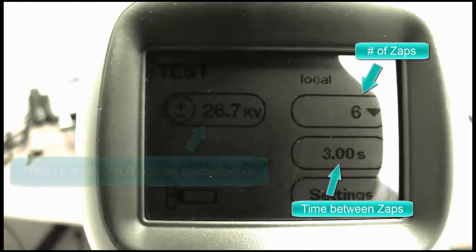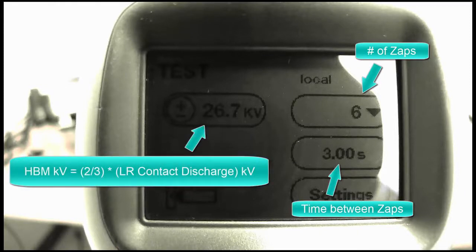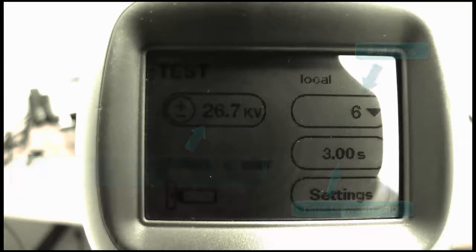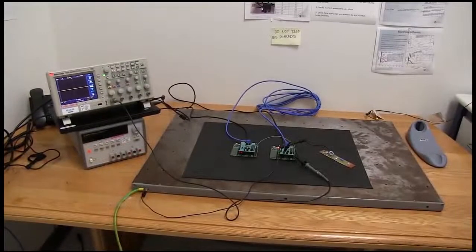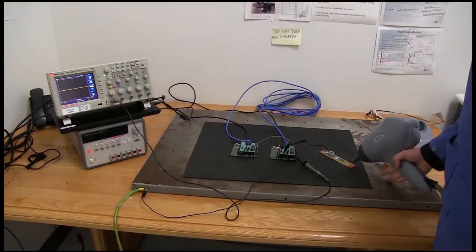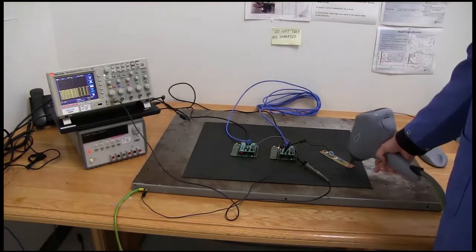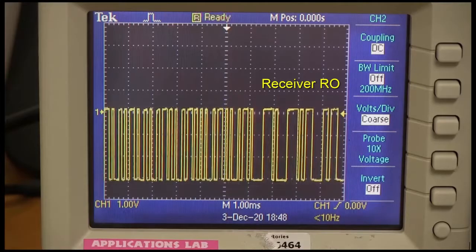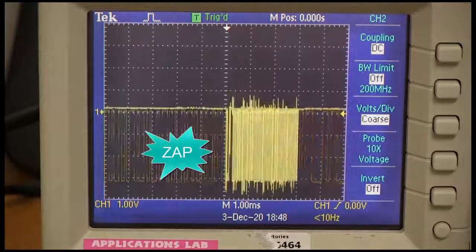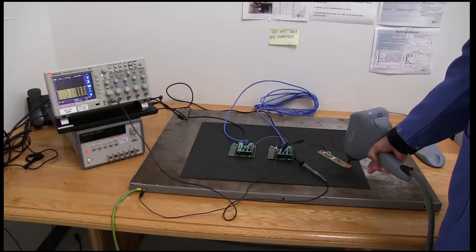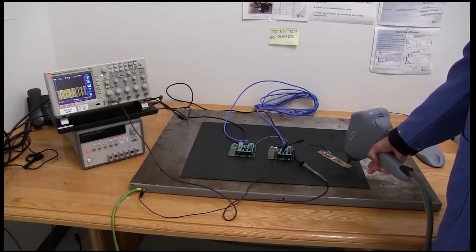The ESD gun is set to 26.7 kilovolts instead of 40 kilovolts. This two-thirds correction factor in pre-charge voltage is needed to adjust the contact peak current value to match the human body model. The same hex message is being repeatedly sent as in the other tests. The data transmission is compromised while the ESD strikes are occurring, but the receiver and transmitter quickly recover and continue to attempt to send and receive the message. As can be seen from the oscilloscope, communication still proceeds after all ESD strikes are applied.